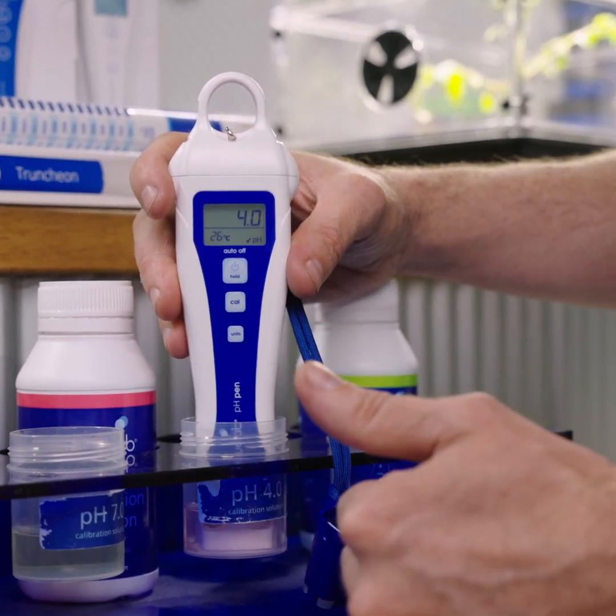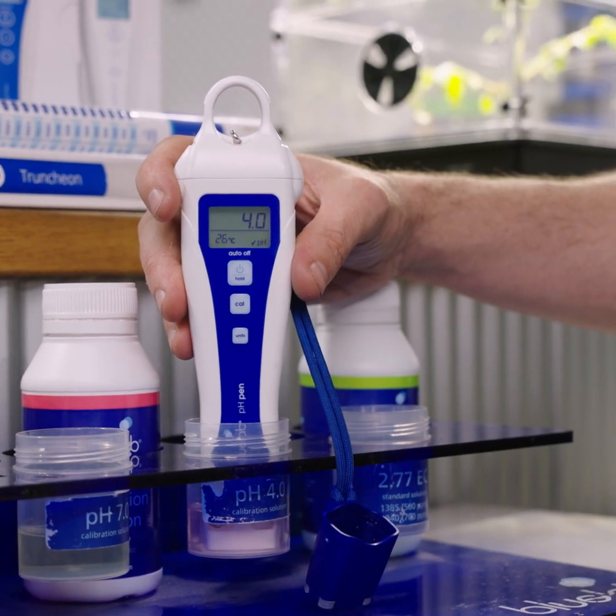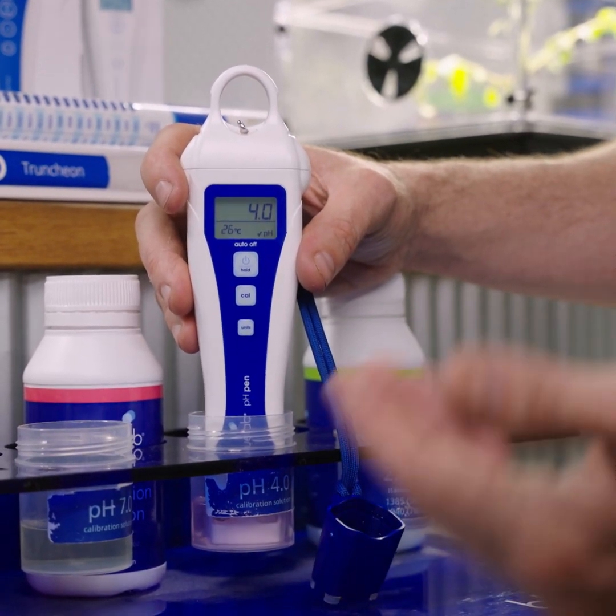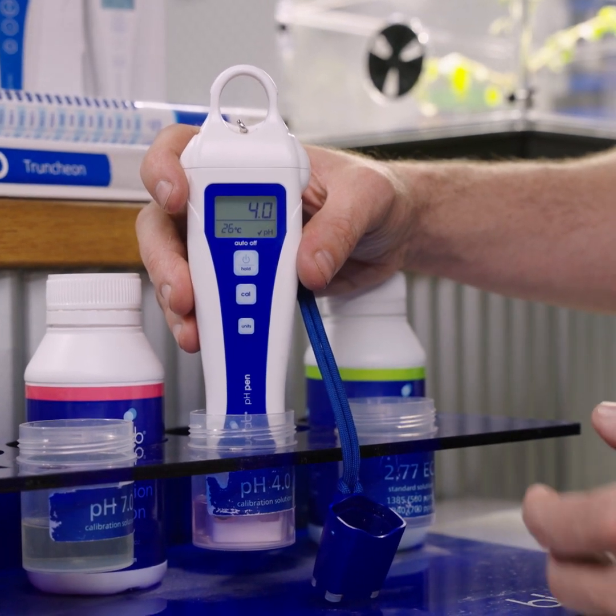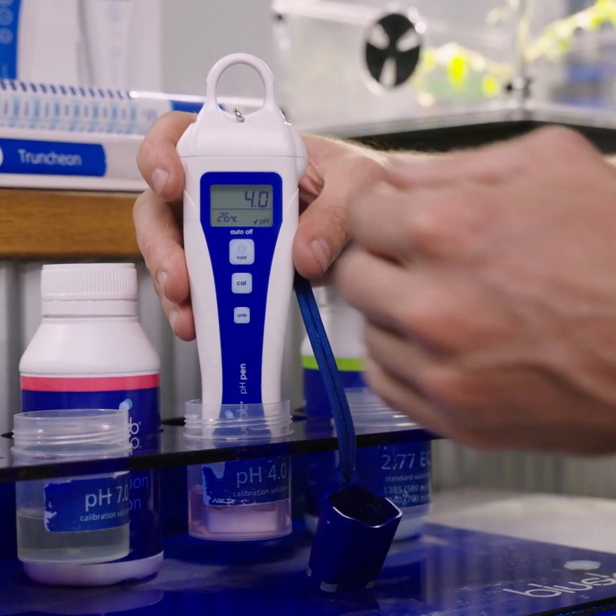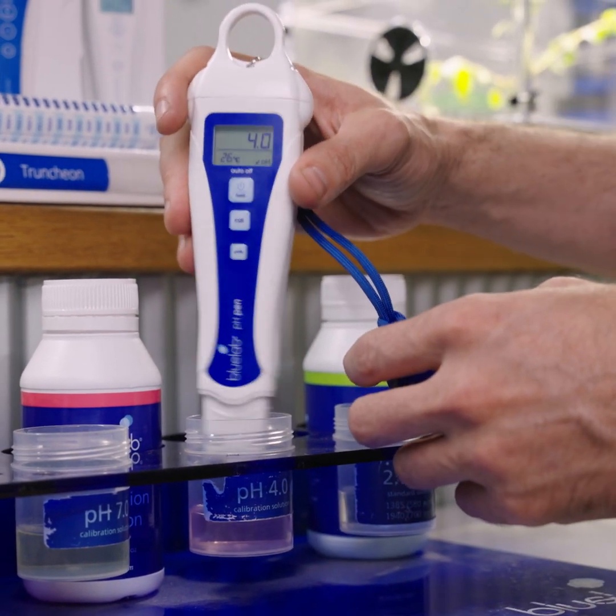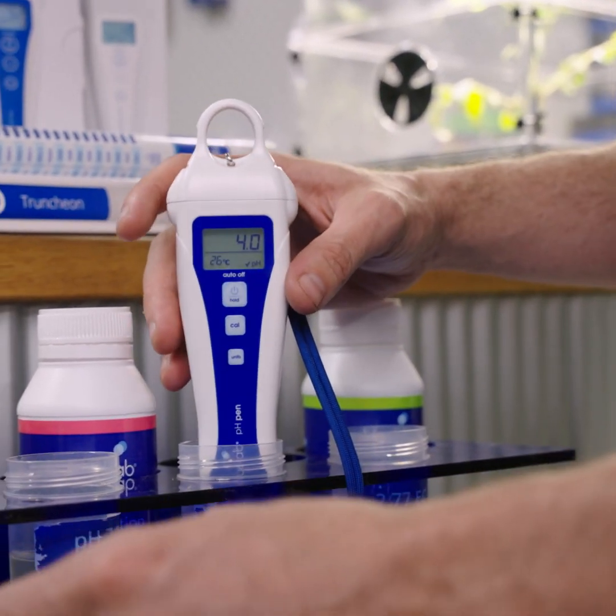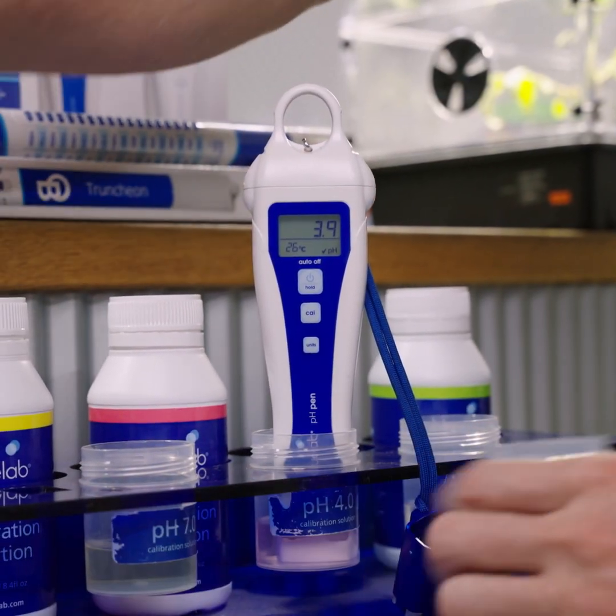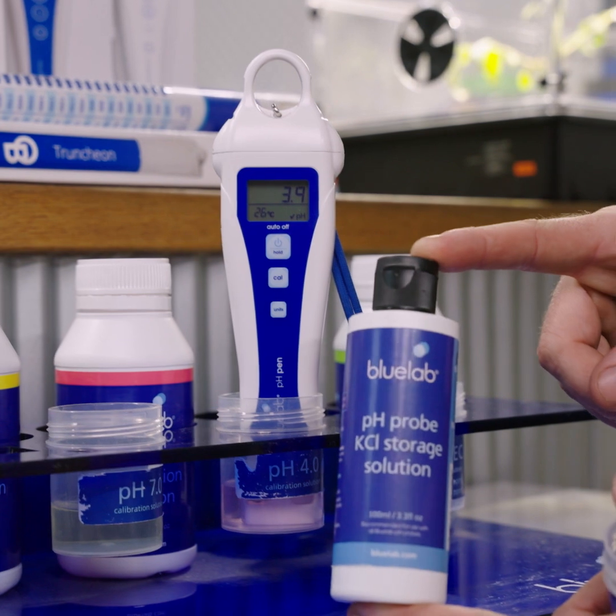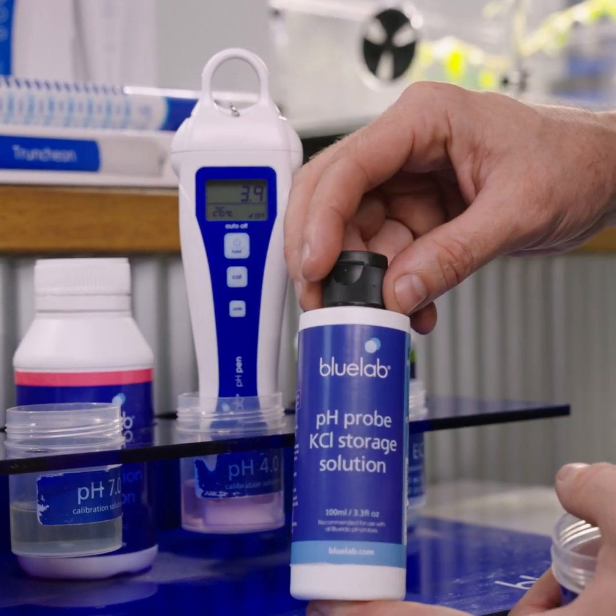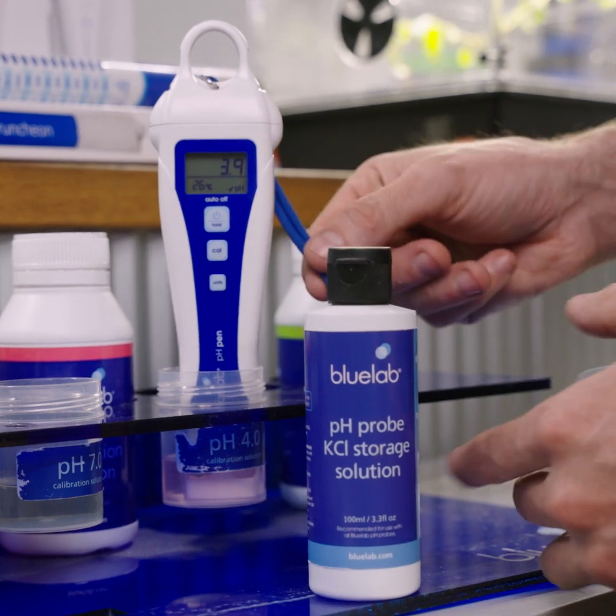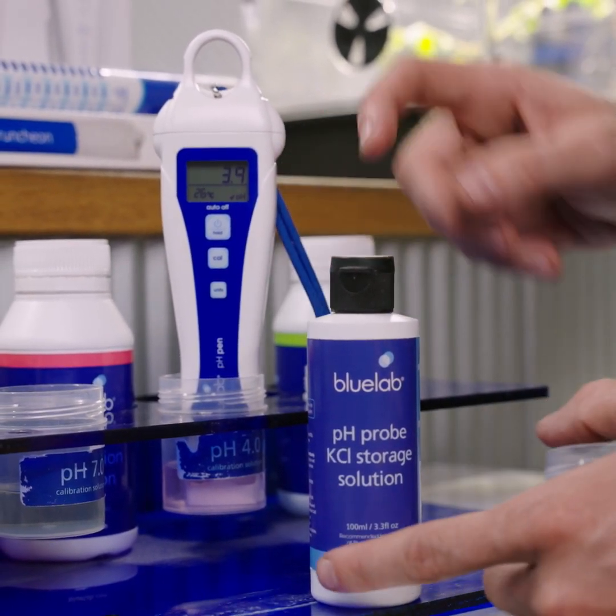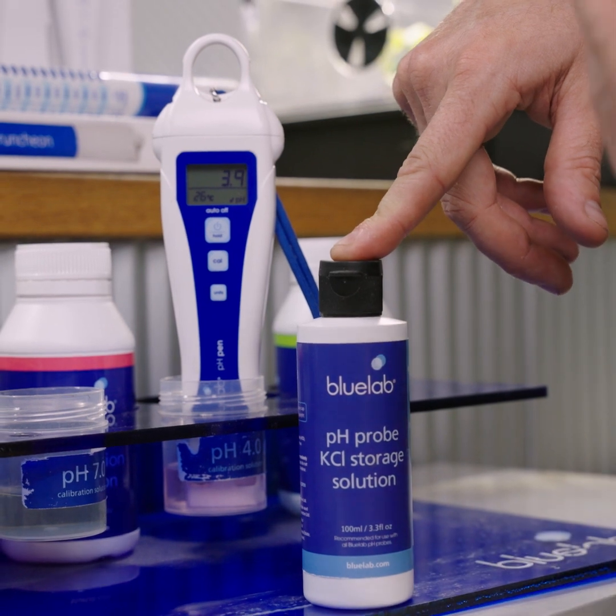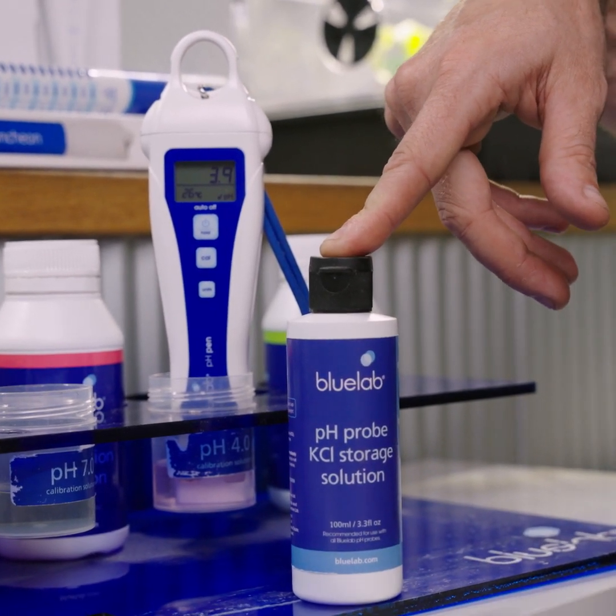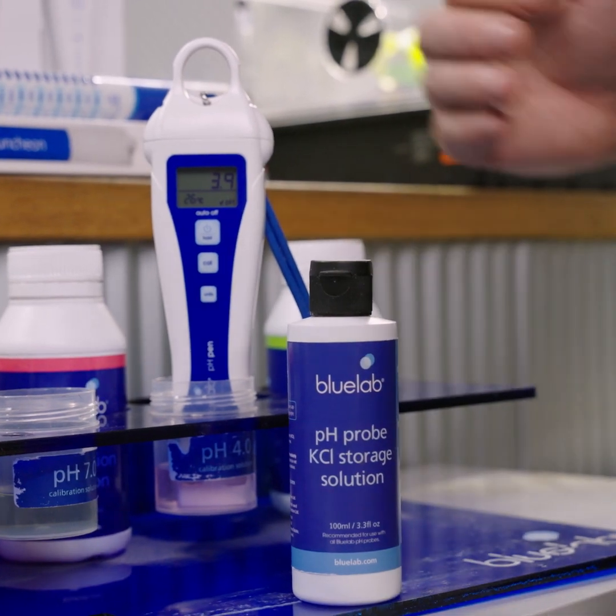So now it has 4 and 7, it'll be able to accurately measure between 4 and 7. Well, it'll be able to accurately measure a wide range of pH, but it's giving it 2 separate points to calibrate off of. So then again, I'll rinse that in clean water, and then after I've rinsed that in clean water, your potassium chloride solution, your probe storage solution. In the cap of the pen, there's a little sponge. Usually just put 1 or 2 drops of this in there and it'll make sure that your probe glass stays clean and sterile and doesn't change its pH very much.